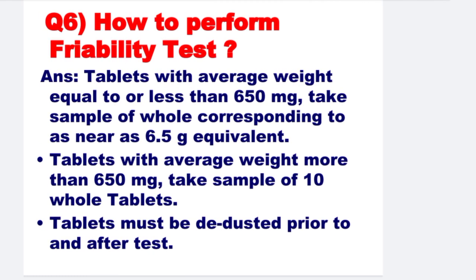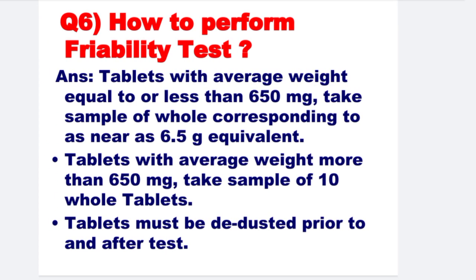Next: How to perform friability test? Tablets with average weight equal to or less than 650 mg: take a sample of whole tablets corresponding to as near as 6.5 grams equivalent. Tablets with average weight more than 650 mg: take a sample of 10 whole tablets. Tablets must be dedusted prior to and after the test.